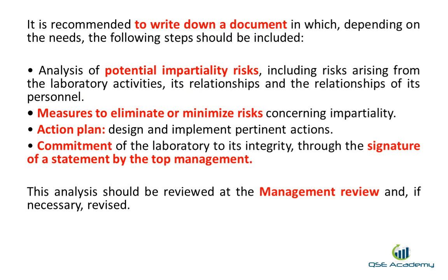Analysis of potential impartiality risks, including risks arising from the laboratory activities, its relationships, and the relationships of its personnel. Measures to eliminate or minimize risks concerning impartiality. Action plan. Design and implement pertinent actions. Commitment of the laboratory to its integrity through the signature of a statement by the top management. This analysis should be reviewed at the management review and, if necessary, revised.